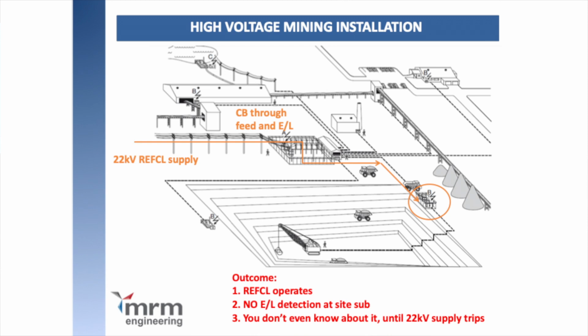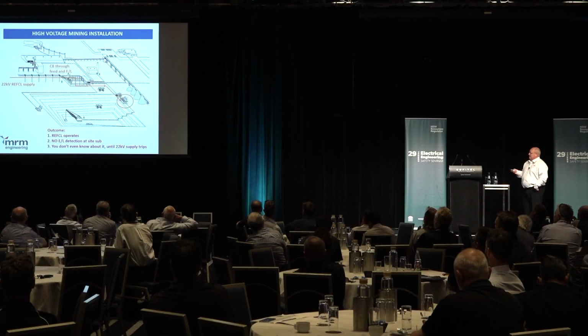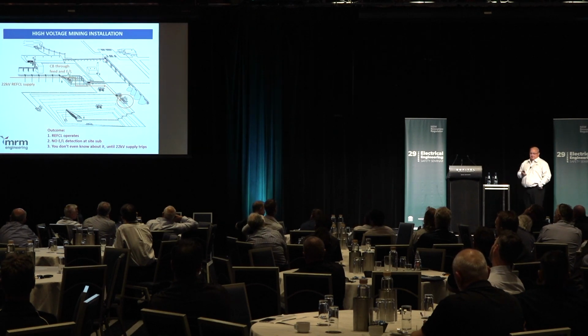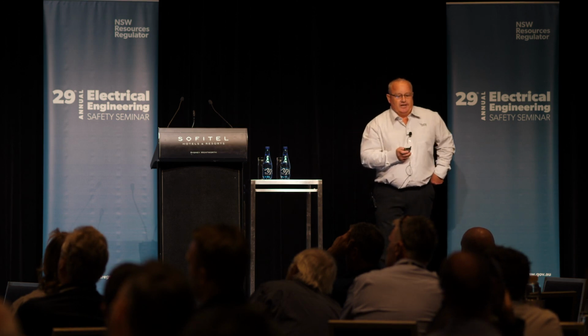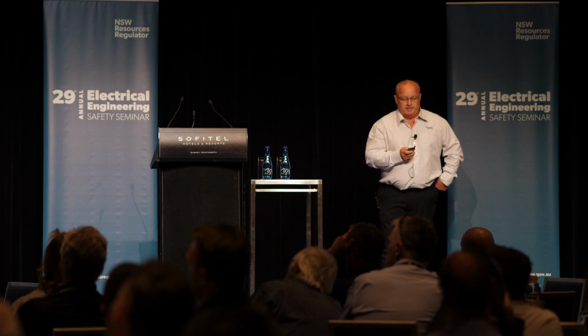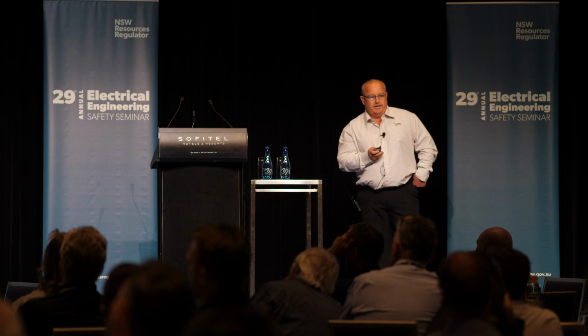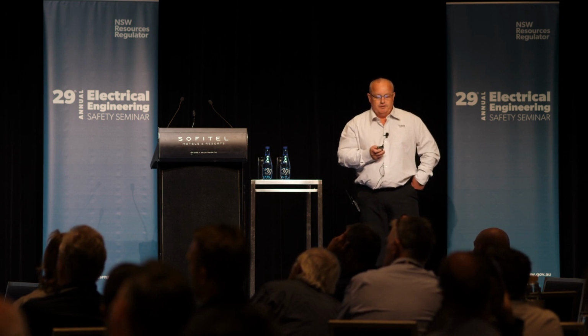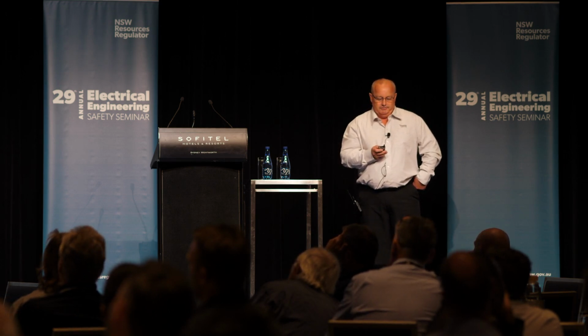So this is just like a typical mining diagram. So you got your 22 kV coming in. I'm assuming in this substation we're just switching through a circuit breaker, and then we're feeding it out to a machine. So on the machine we have a fault. We've got our earth leakage protection stuff set in here. It's not going to work. We just took the upstream protection from the ground fault neutralizer or even a solid state one won't let our system clear. It'll block the current. You won't detect the ground fault, and you probably won't even know it's happened.